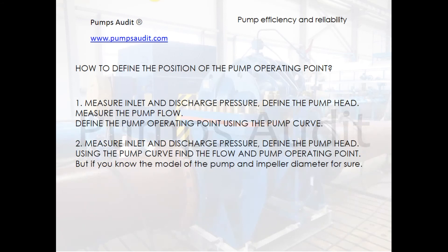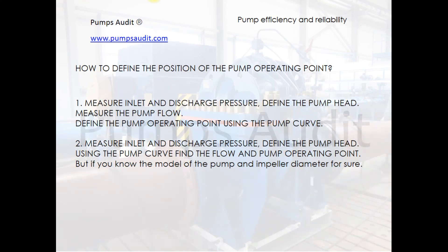First: measure inlet and discharge pressure, define the pump head, measure the pump flow, and find the operating point using the pump curve. In many cases, it is not possible to measure pump flow directly. In that case, measure inlet and discharge pressure, define the pump head, and use the pump curve to find the flow and the operating point — provided you know the pump model and impeller diameter.